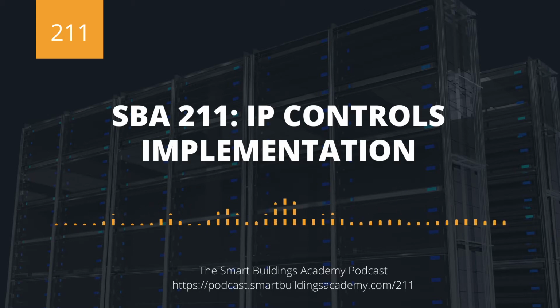Now, what we're looking at with IP controls is that they actually more resemble a plant controller. If you all are familiar with those hybrid supervisory field controller plant controllers that came out around 2008, 2009, that was their big year, their big push. They had IOM on them, input-output modules, or they just had IO on them. But yet they had supervisory functionality.